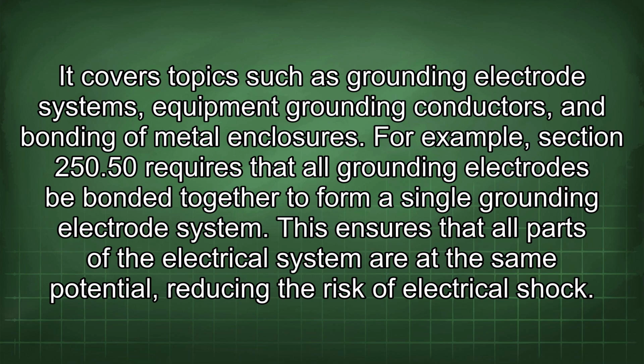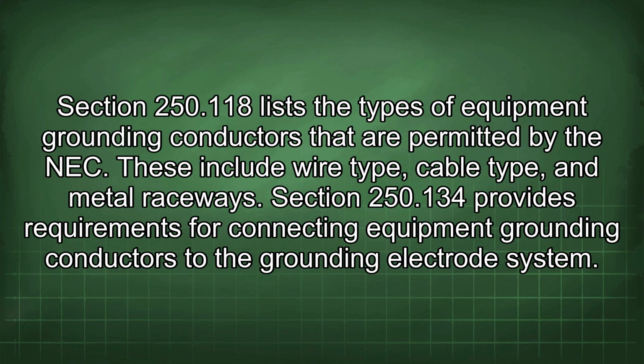This ensures that all parts of the electrical system are at the same potential, reducing the risk of electrical shock. Section 250.118 lists the types of equipment grounding conductors that are permitted by the NEC. These include wire type, cable type, and metal raceways. Section 250.134 provides requirements for connecting equipment grounding conductors to the grounding electrode system.